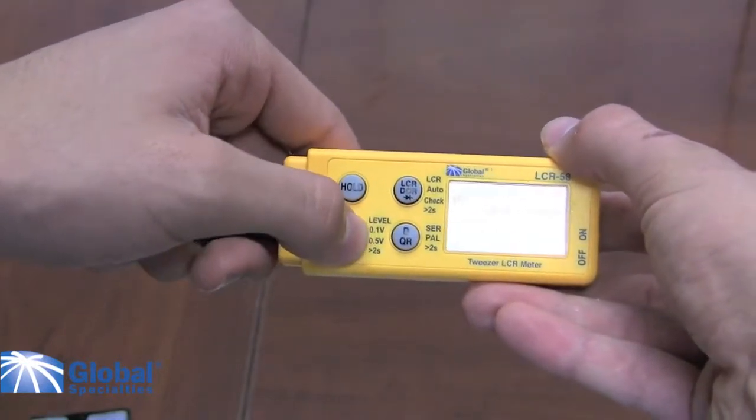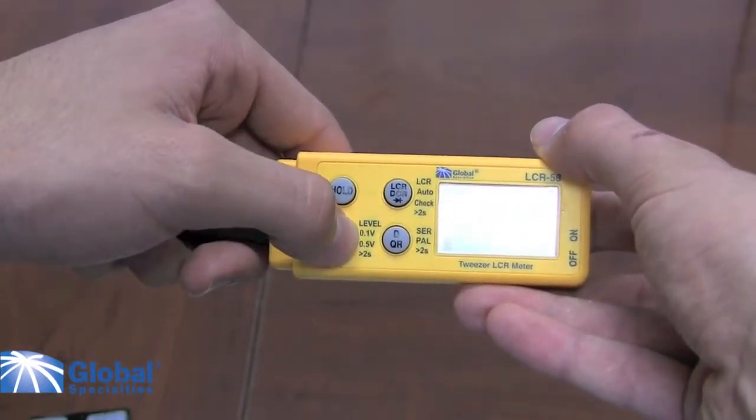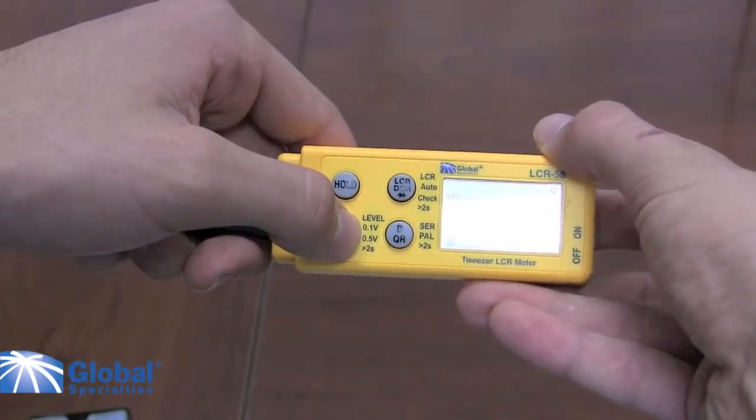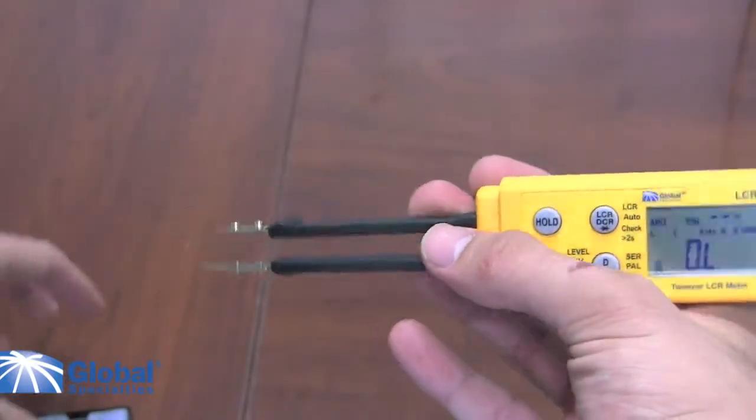Let's try inductance. The first thing we need to do is select a frequency range that we will be measuring in. In this case, in order to get a high precision, we will be using a 1 kHz setting.